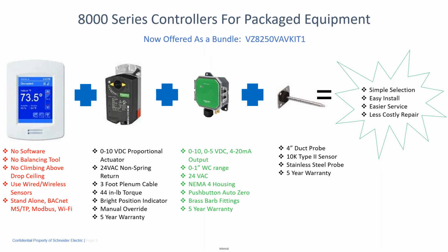Again, this makes it very easy to select, very easy to install. When you service it, if something goes bad, then you can replace each one of the individual components as opposed to replacing a complete VAV box controller. So you can replace just the pressure transducer, just the actuator, just the temperature sensor.